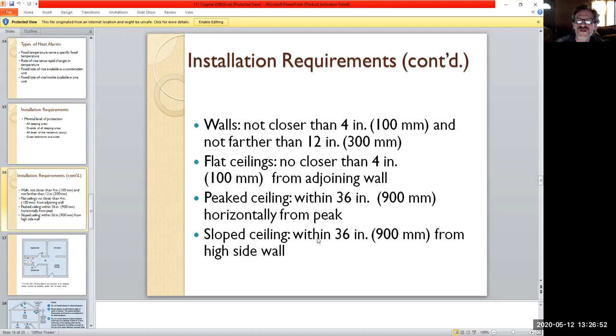For pitched ceilings, like church peaks - vaulted ceilings are becoming more popular - the rule of thumb is within 36 inches of where the peak is at the top, no further away than that, because the peak is where the heat and smoke rise and condense. Slope ceilings are the same type of deal - any kind of pitch to a ceiling other than flat follows this rule of thumb.